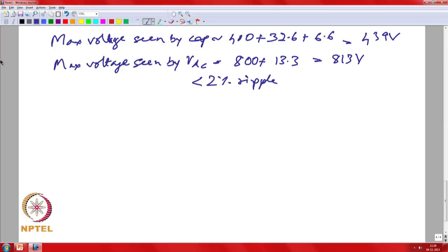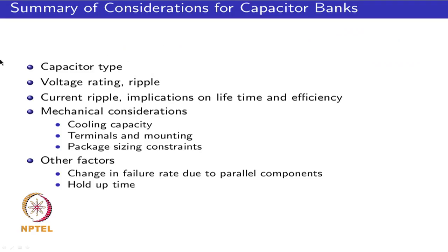Looking at the overall design of the DC bus capacitor bank: the first thing to decide is the type of capacitor. In a voltage source inverter, an electrolytic capacitor on the DC bus is common. People have started looking at very high reliability inverters where electrolytic capacitors might be eliminated and polypropylene capacitors used instead, though their capacitance value is quite small and a large bank would be needed. The voltage rating from both DC and ripple perspectives is important. The current ripple has implications on life and efficiency. If you are tight on these two factors, one might consider adding more capacitors in parallel.